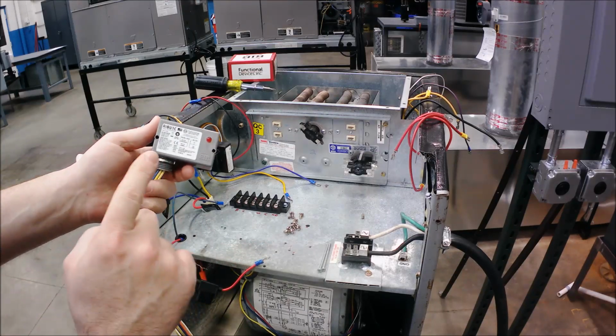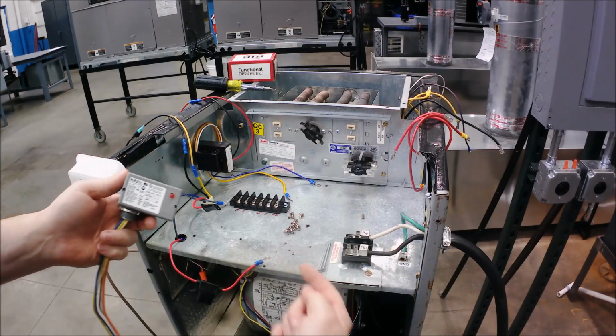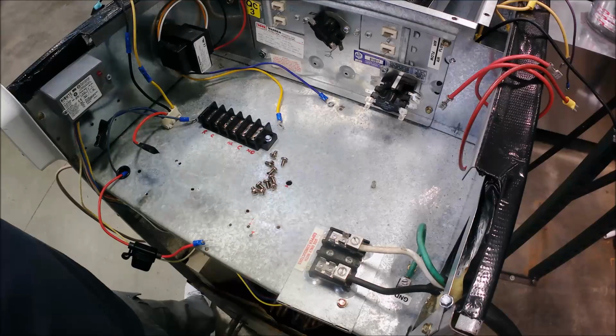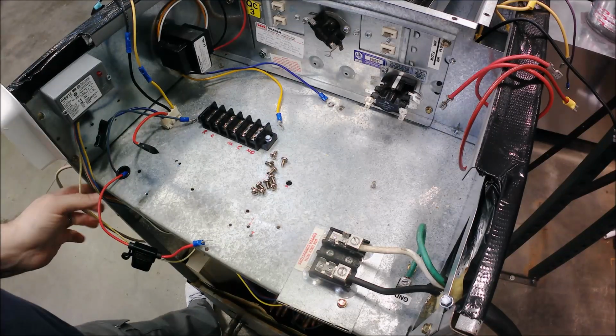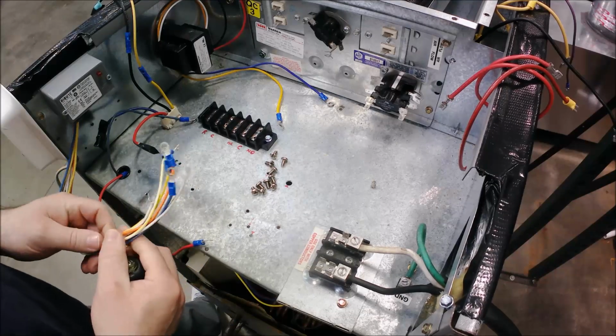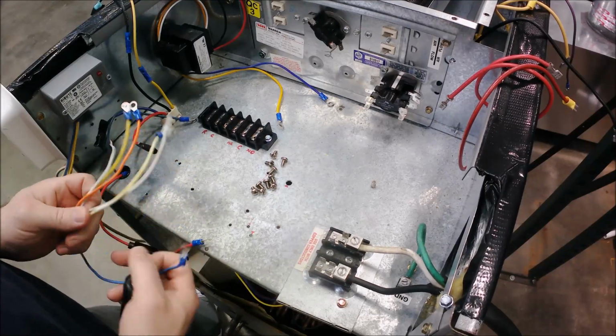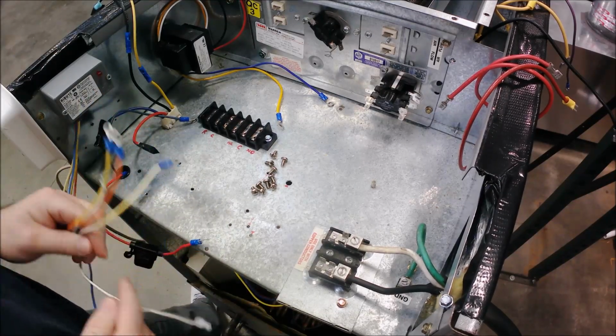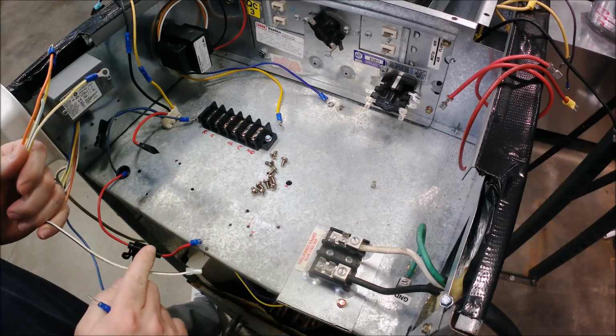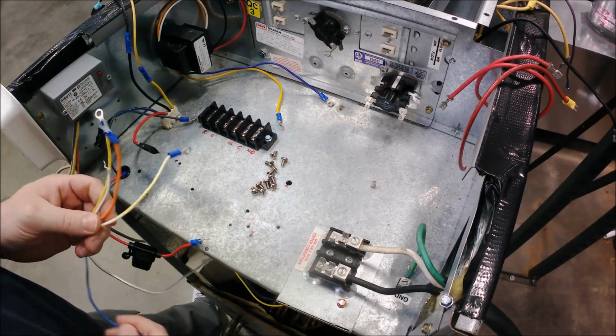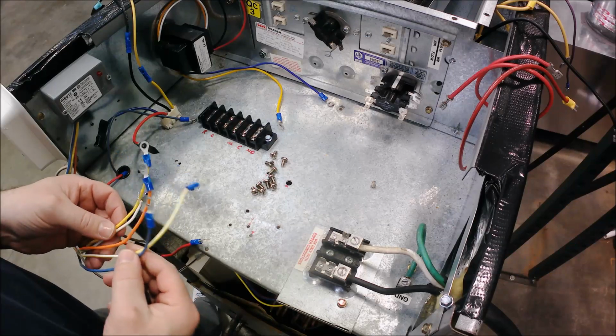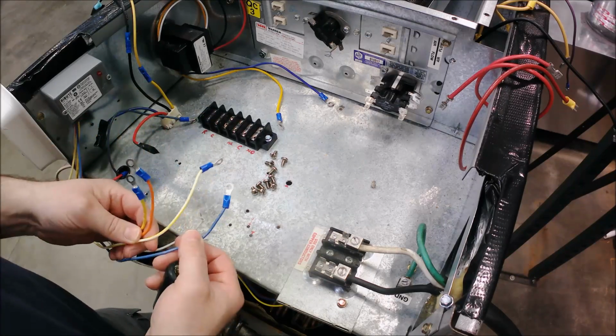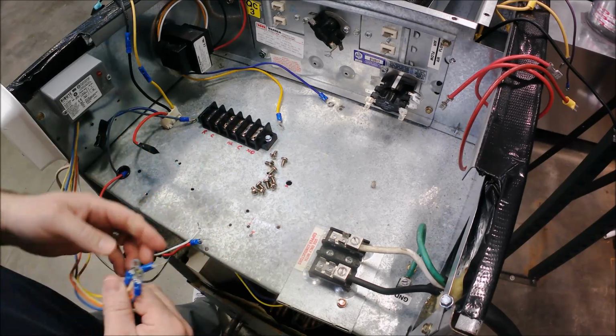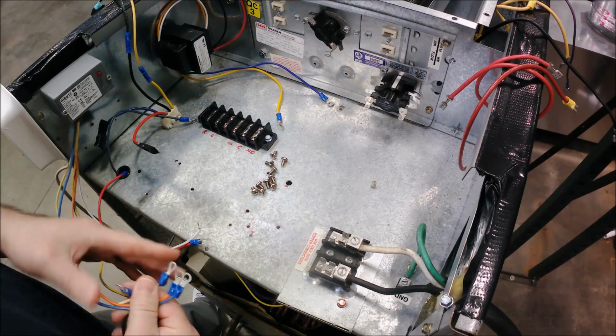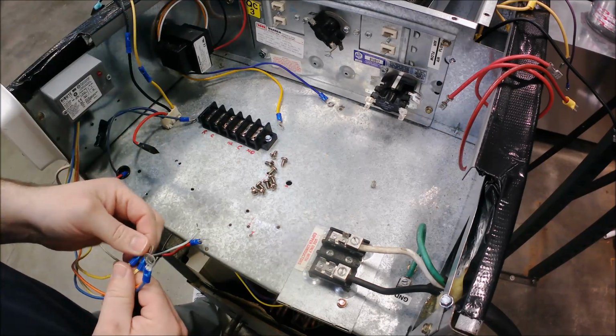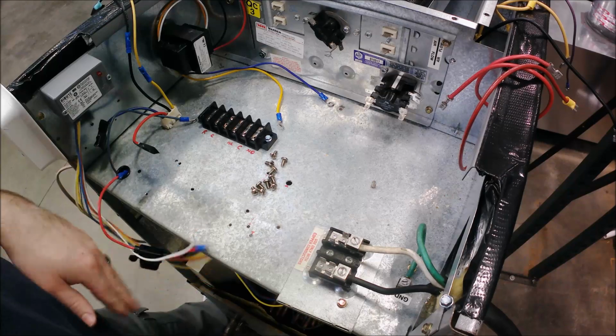And I'm going to mount this rib relay inside the air handler. I'm going to start out by wiring the low voltage. Now I've got all my terminals for my rib relay right here, and I have capped off the 120 volt connection that we're not going to use. So I'll wrap it up and curl it under here, but everything else is going to have a ring on it, so we can easily put it under these screws for this terminal block, and it'll make it easier for voltage checks or future use.